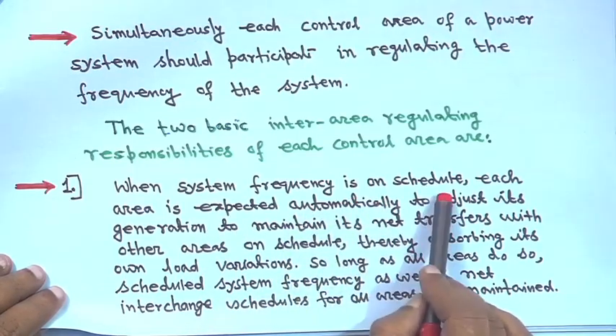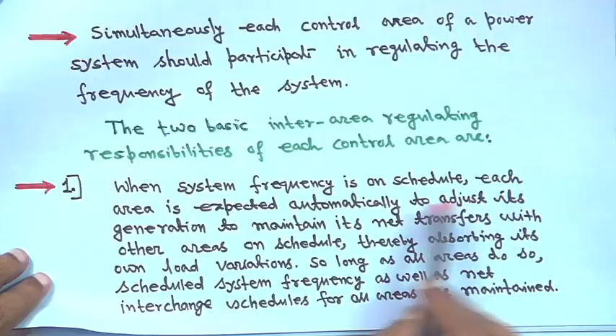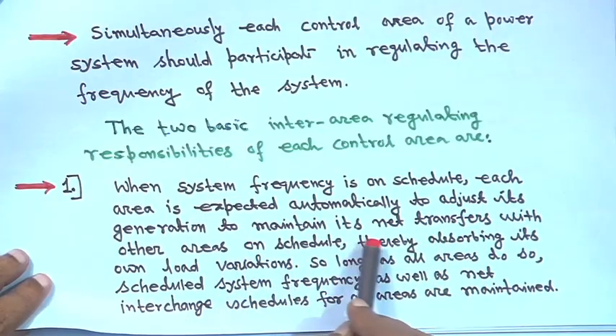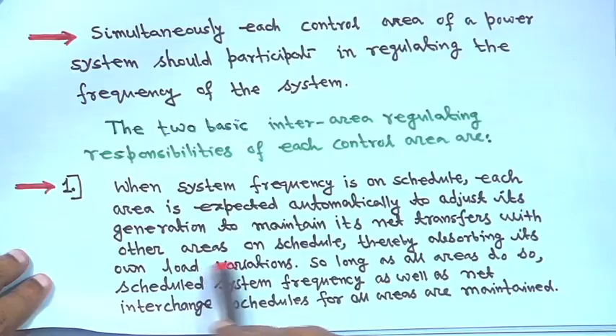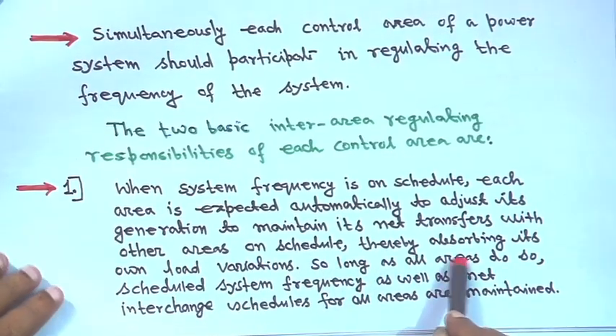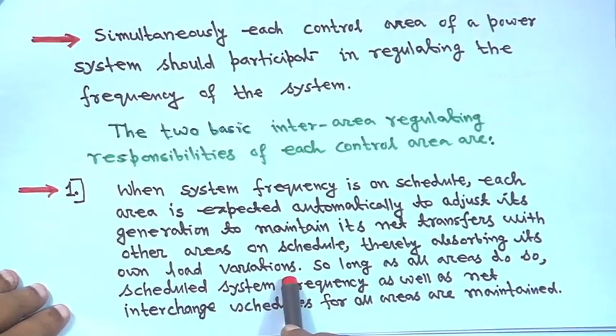When system frequency is on schedule, each area is expected automatically to adjust its generation to maintain its net transfer with other areas on schedule, thereby absorbing its own load and own load variation. So long as all areas do so, schedule system frequency as well as net interchange schedule for all areas are maintained.